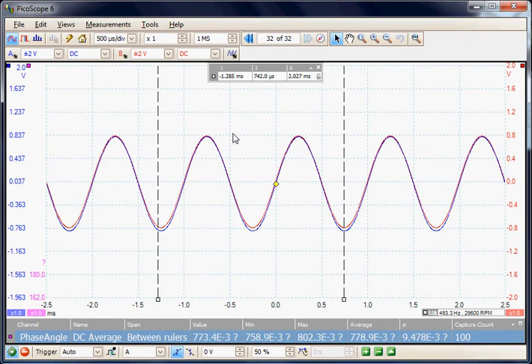But before making any measurements, it's very important to compensate the probes so that when they are connected to the same point, they have zero degrees phase shift. So here we can see such an example where two probes are connected to the same generator, and we have a very low phase shift.